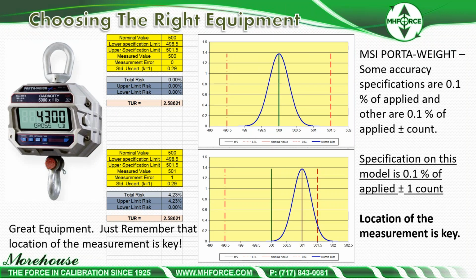Here we can look at some other ones. This is an MSI Porta-Weight, a very good instrument. Most of them, about 80%, come in and hold their calibration. It's pretty amazing. But it's just an example where the location of the measurement is key. The specification of the unit model is 0.1% of applied plus or minus one count. If we look at this when the measurement's perfect, measured value up here of 500. And then if we look at it down here when it's 501.